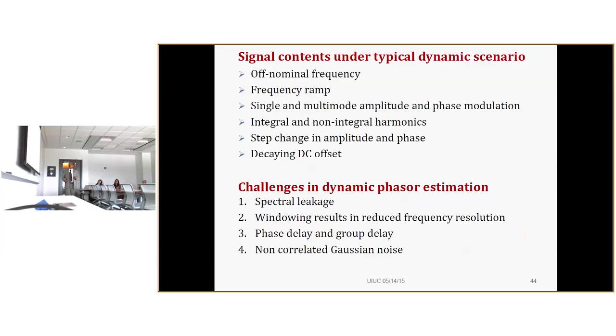Now, why is it challenging? These are the typical signals which are present at off-nominal frequency. Frequency may be ramping down and ramping up. You may have single or multimode oscillations present. You may have harmonics present, which may be integral or non-integral. You may have step change of amplitude and phase, DC offset. And while you are monitoring through PMUs, some additional challenges come because of spectral leakage, windowing effect, phase delay and group delay because of the anti-aliasing filter, and noise which may be non-correlated noise.